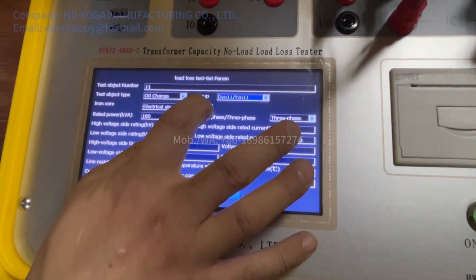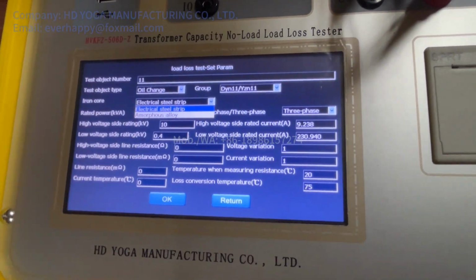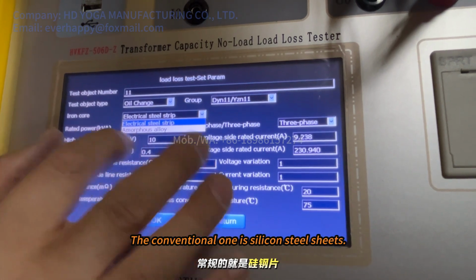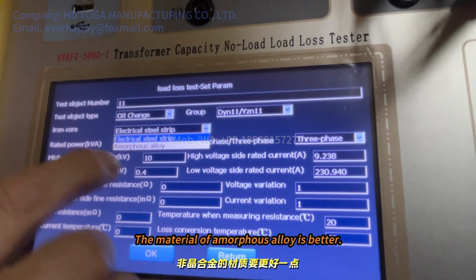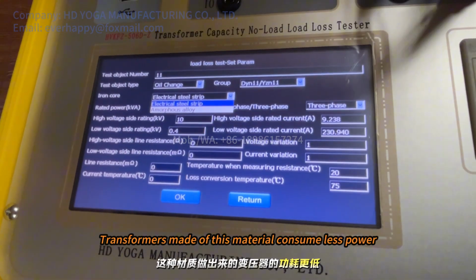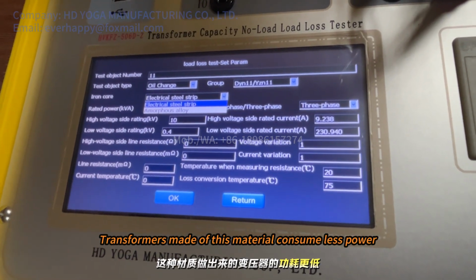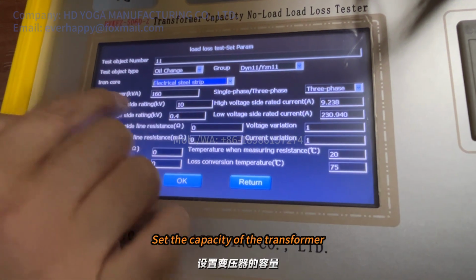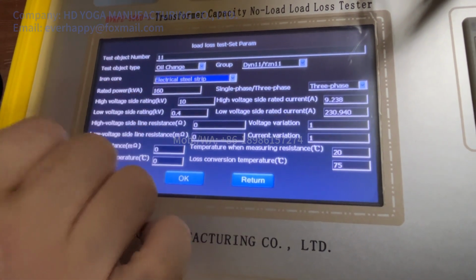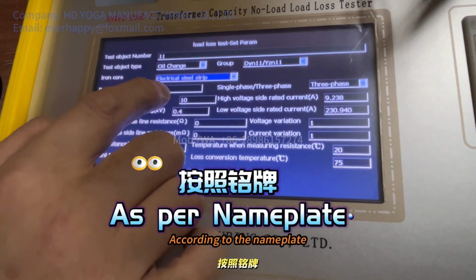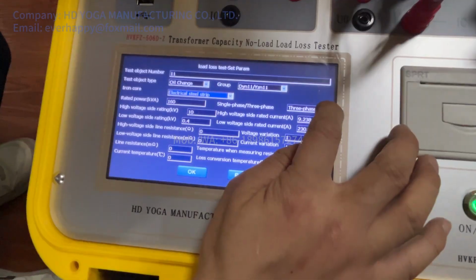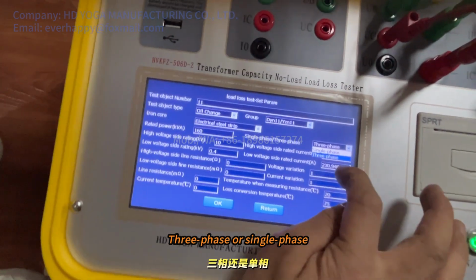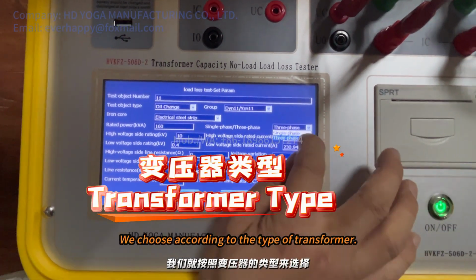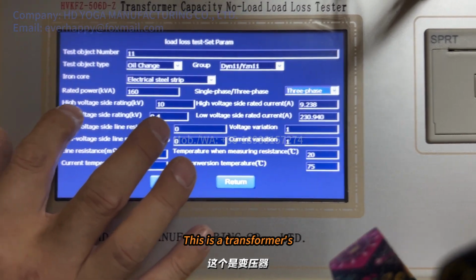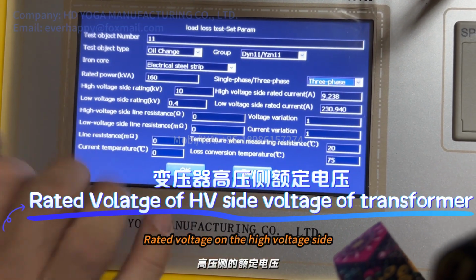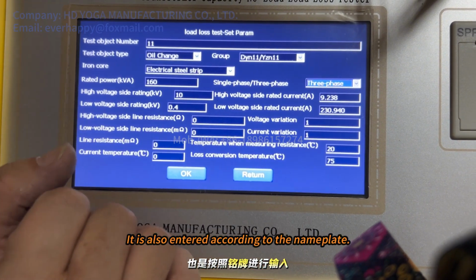Material of iron core: silicon steel sheet and amorphous alloy. The conventional one is silicon steel sheet. The material of amorphous alloy is better. Transformers made of this material consume less power. Set the capacity of the transformer according to the nameplate. Enter as per the nameplate. 3-phase or single phase, we choose according to the type of transformer. This is the transformer's rated voltage on the high voltage side. It is also entered according to the nameplate.